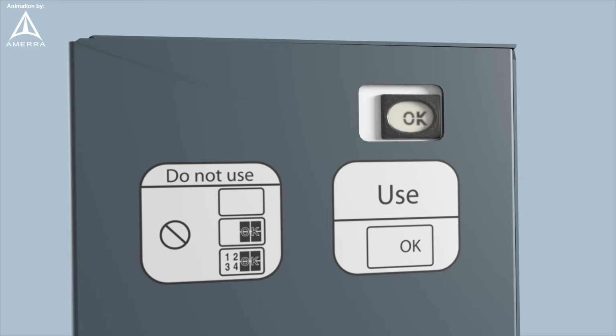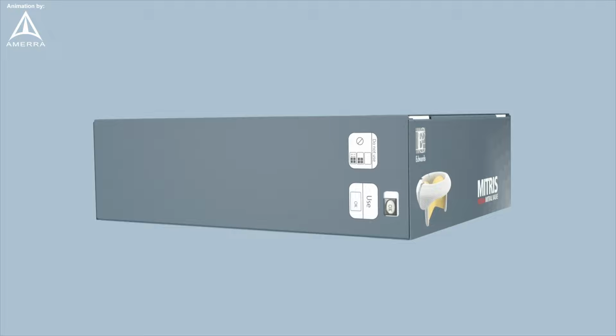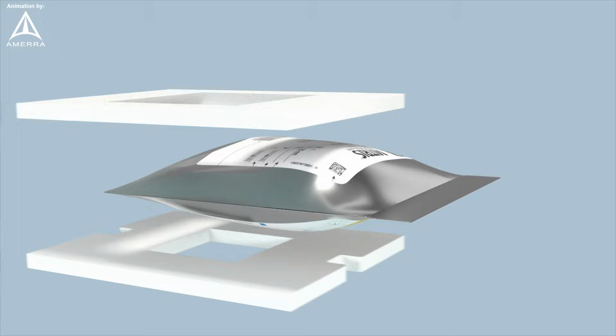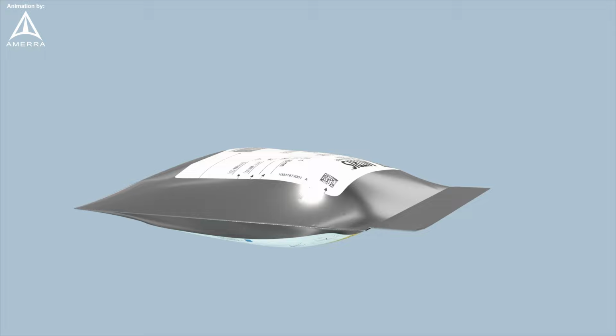Once you have sized the Mitris Resilia valve, verify that the tag alert, visible through the shelf carton, indicates the valve is okay to use. Only use the valve if the tag alert reads OK. Open the carton after confirming that the status is OK. Remove the foil pouch from the carton in the non-sterile field. Examine the foil pouch for evidence of damage and broken or missing seals.